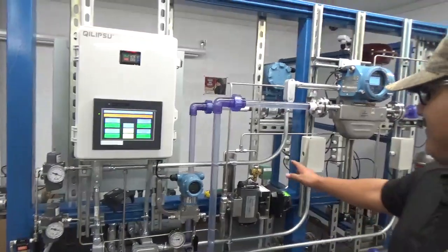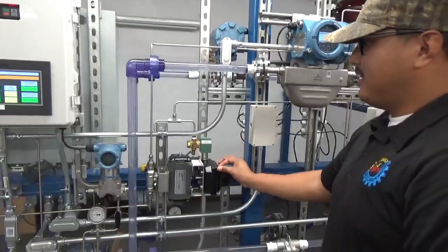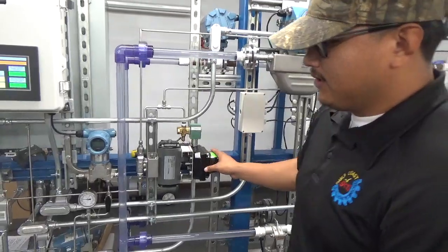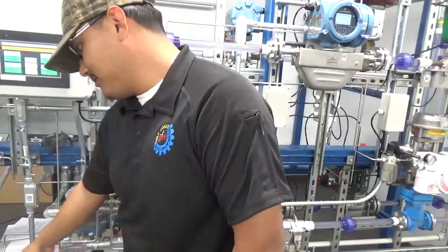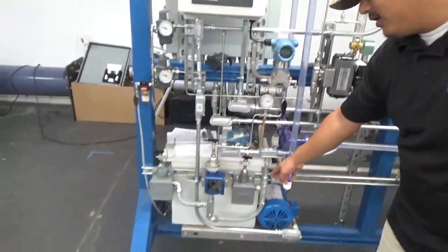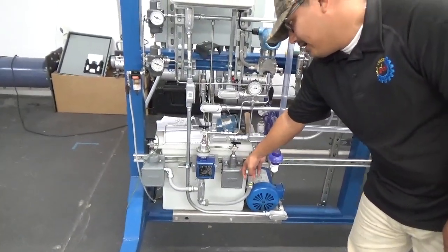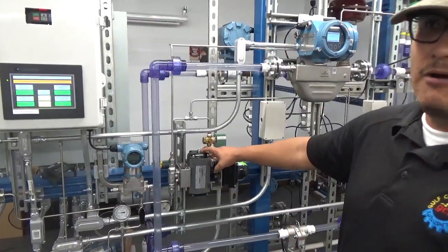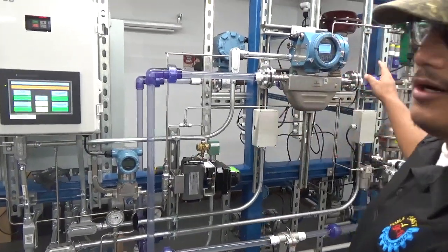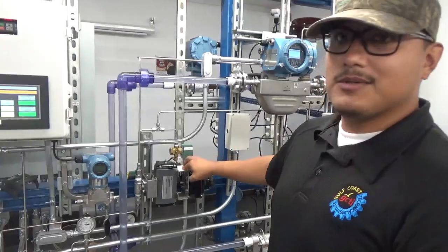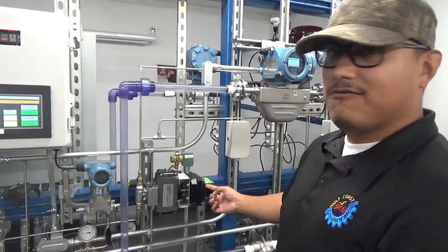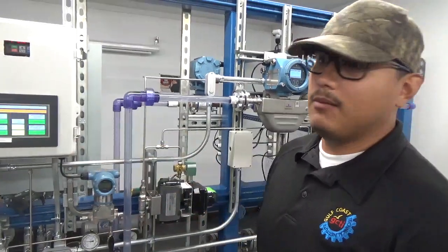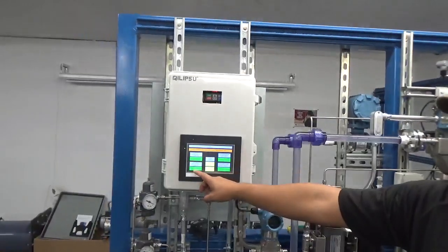And then we have this actuator valve that I still have to wire up. This is going to end up letting me know there's actually air present. So I have 2 pressure switches that are measuring flow, while one is measuring the air supply. This is going to give me feedback if I actually have air present, because this one requires about 50 psi, while the rest require about 40. So once this one stops getting the pressure that it needs, it's going to send me a feedback signal that's saying that the pressure is deactivating, which is going to send me another alarm that I'm going to go ahead and activate, which is this one down here.